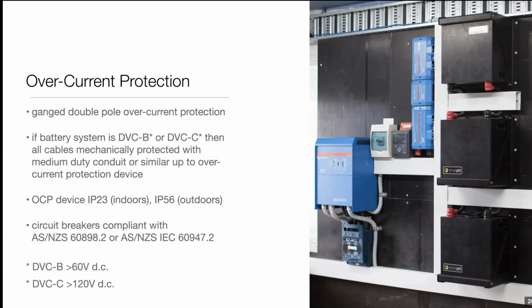We deem that batteries shouldn't be installed at wet or damp locations, and therefore DVC A is systems up to 60 volts. So anything that's DVC A, that doesn't go over 60 volts for more than 0.2 of a second under any operating condition, is deemed to be equivalent to ELV. And in terms of licensing, that would mean it doesn't require an electrical license, but it does need to be a competent person, defined as someone who has gained the necessary skills and knowledge through training. So a competent person can install systems up to 60 volts, but once you go over 60 volts for more than 0.2 of a second, you're in DVC B land, until you get to 120 volts, and then you're in DVC C land.